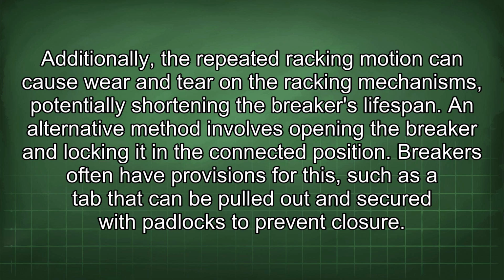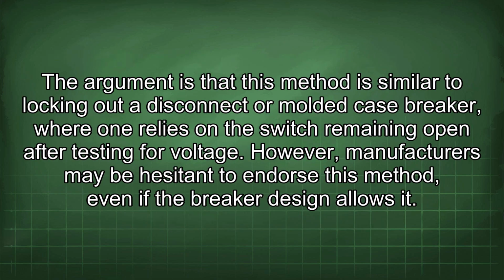An alternative method involves opening the breaker and locking it in the connected position. Breakers often have provisions for this, such as a tab that can be pulled out and secured with padlocks to prevent closure. The argument is that this method is similar to locking out a disconnect or molded case breaker, where one relies on the switch remaining open after testing for voltage. However, manufacturers may be hesitant to endorse this method, even if the breaker design allows it.